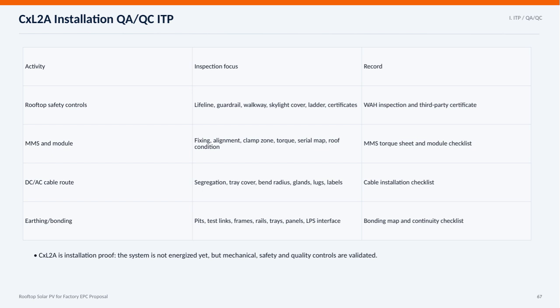The DC and AC cable routing ensures proper segregation, tray covers, bend radius, glands, lugs, and labels, recorded via cable installation checklists. Lastly, earthing and bonding are verified through inspection of pits, test links, frames, rails, trays, panels, and lightning protection system interfaces, supported by bonding maps and continuity checklists.